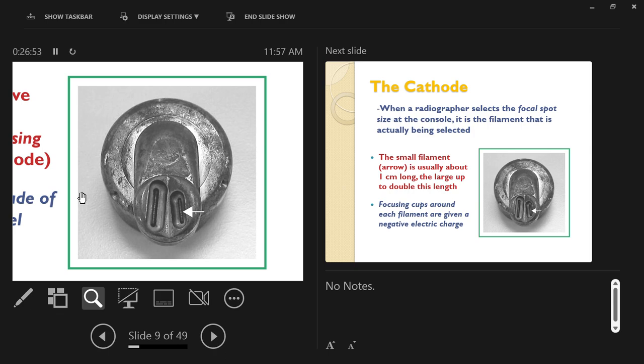In x-ray terminology, the source of x-rays is referred to as the focal spot. A large filament creates a large focal spot on the anode disc — a large area where the x-rays originate from, like all the lights in the room. A small filament makes a small focal spot, equivalent to a small flashlight, giving a much clearer shadow.